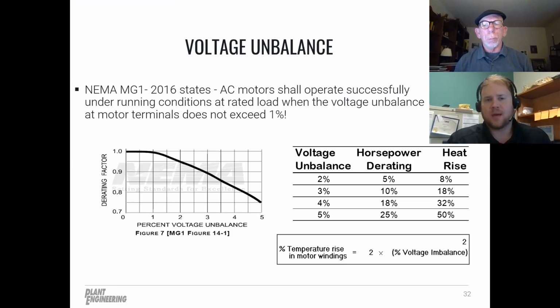Another thing, voltage imbalance directly leads to current unbalance. One industry rule of thumb I've always heard is that for every 1% voltage imbalance, a motor is going to show 7 to 8% current unbalance. And it's not just a rule of thumb. I see it really every day, in motor testing and stuff like that. High current unbalance is very detrimental to motor operating conditions, and higher currents on the individual phases lead to hot spots in the windings, and then again, early failure.